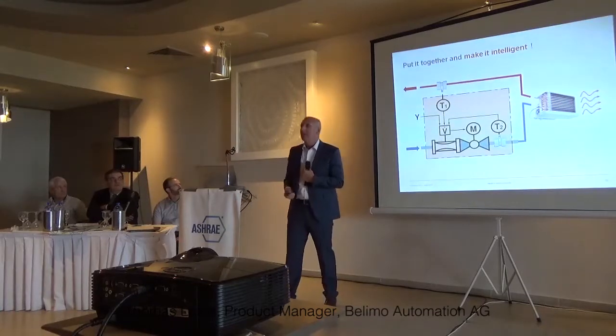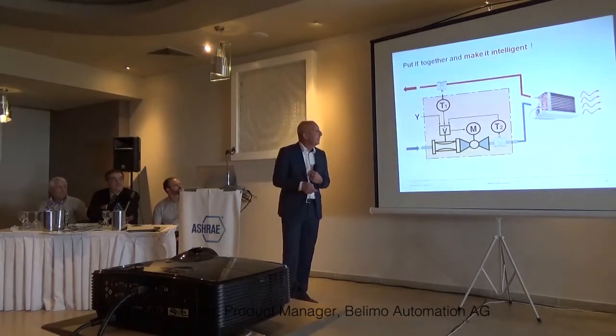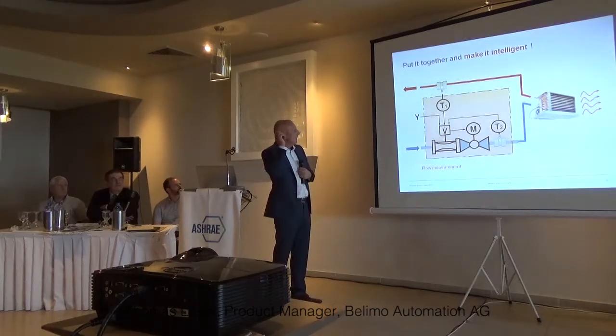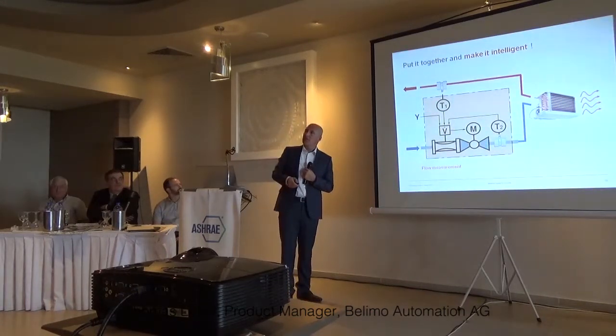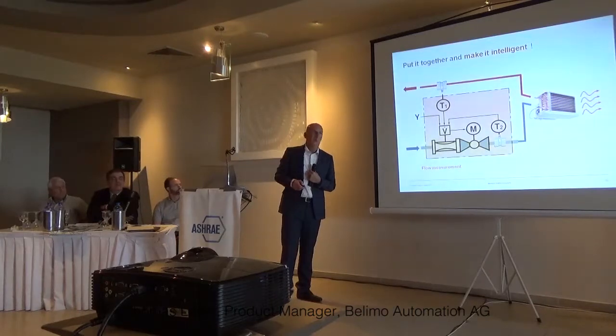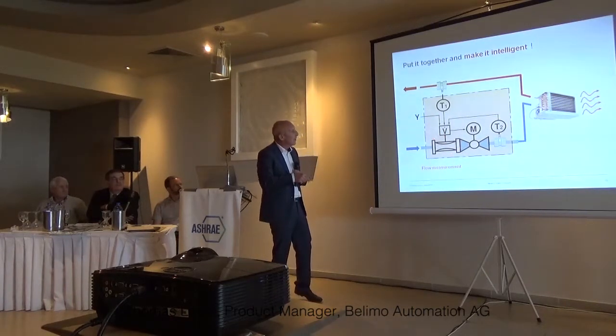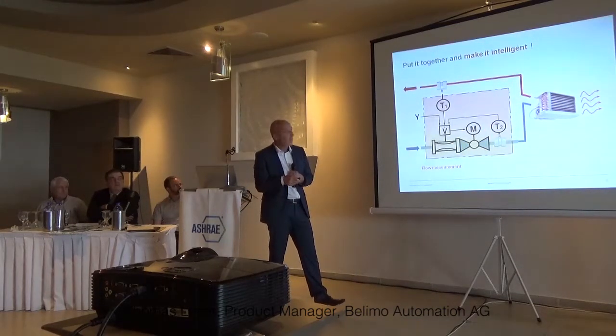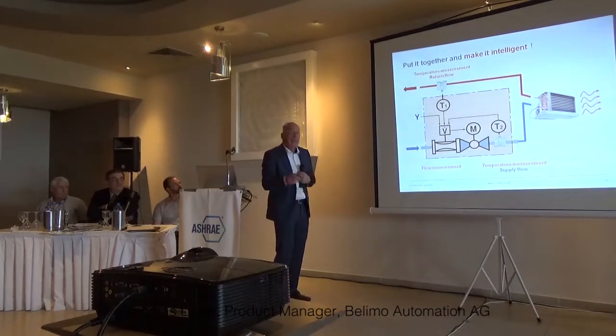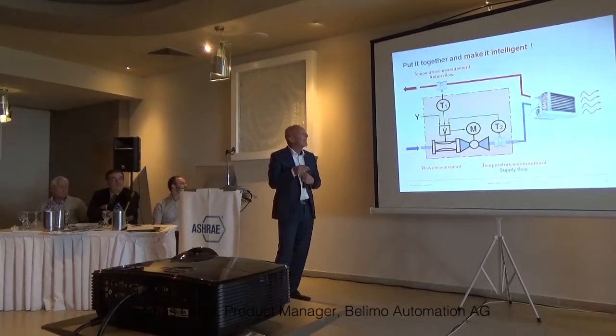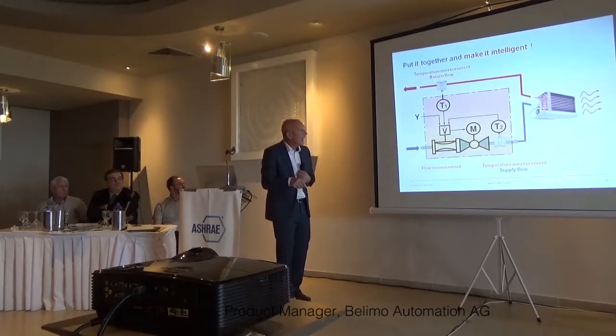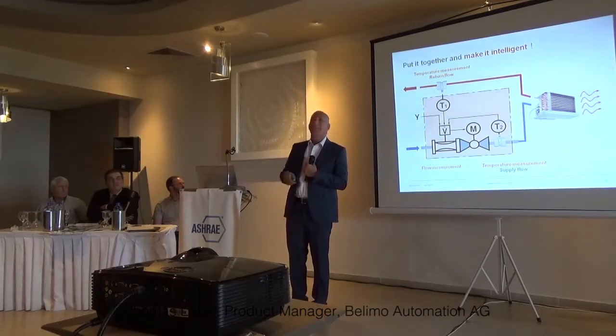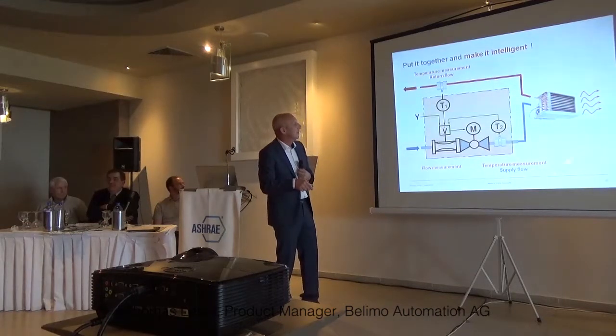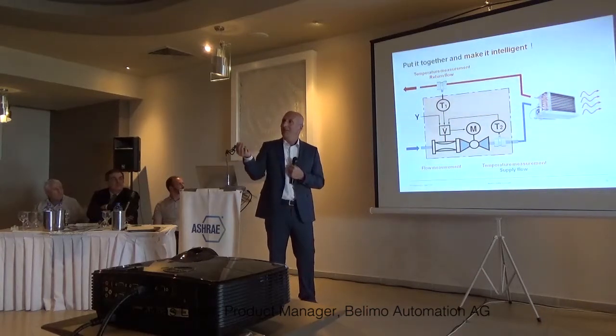The idea came, make one valve out of it. One valve, similar to the electronic pressure-independent one that I mentioned before. It comes with a flow meter. It comes with a more or less ordinary control valve. But then you have to add something, temperature measurement in the return and the supply. And if I measure my temperature in the supply and the return across my coil, this is delta T.